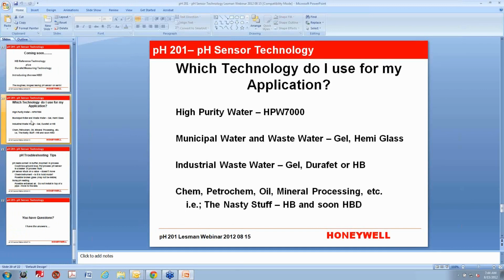So, what do you use for your application? Well, if I could give you a list that would answer all of those questions, I would not have been doing this for 20 years, because that's a lot of what I do: help people choose what sort of technologies are going to be best for their process. In general, if you have high purity water, you need something like an HPW 7000, which is our high purity water device that has a flowing reference. It's made of stainless steel. It has a good mixing chamber. It has a solution ground to give you a very stable measurement. And that's really the only thing that will work in high purity water. High purity water is any water that is less than 20 microsiemens conductivity.